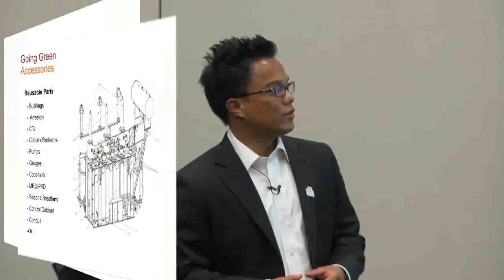Oftentimes we are able to reuse parts of the windings, whether it's A, B, or C windings, but there are times when you can't reuse them. One of the additional benefits to redesigning the copper is that the older transformers can be redesigned to meet today's short circuit withstands. So if you are rewinding your transformer, scrapping the copper itself, you can rebuild the transformer. You can either upgrade it or you can improve the short circuit capability of the transformers.